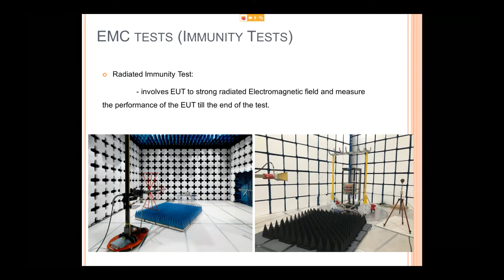The test involves exposing the EUT to strong radiated immunity and measuring its performance until the end of the test. This is the radiated immunity test. The emission is sent out from an antenna, so the complete anechoic chamber will have radiation like 20 volts per meter or 10 volts per meter. The EUT's performance is monitored until the end of the test, and then it's determined that the EUT can withstand up to that level of radiation.